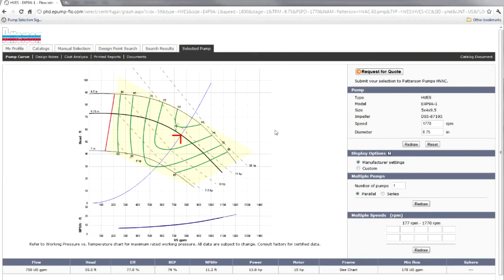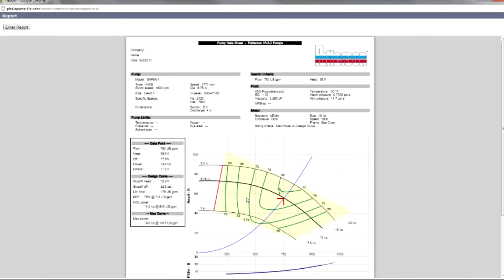Now the nice thing, if you don't want to estimate your brake horsepower, is to click up here on printed reports and go to the pump data sheet. You could fill in the company, the name, the additional information, or just submit it as is. This will give you all the details that you'll ever need for this pump. With this data sheet, it gives us all the information about our pump: the rotating speed, the size of the diameter, the trim of the impeller, and then down along the left-hand side here, it gives us our power, our brake horsepower at that point.